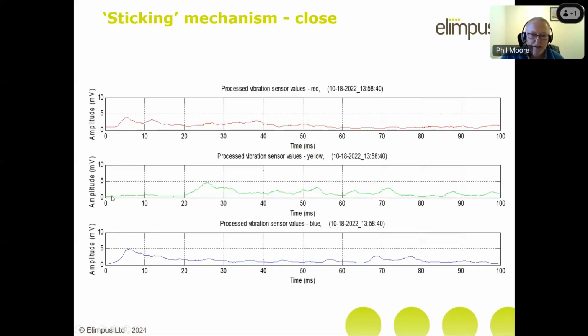The yellow is about 15, 16, 17, 18 milliseconds after the other 2, and that is a problem because most circuit breakers have a phases not together alarm, and what that means is if it closes and it can see that in fact only 2 of the phases are connected, it automatically reopens straight away, because having 2 phases connected will generate a lot of negative phase sequence and zero phase sequence currents, which are bad for the system, so they'll take it out. Now this wasn't at that point, but you can see it was going to get pretty close to it.